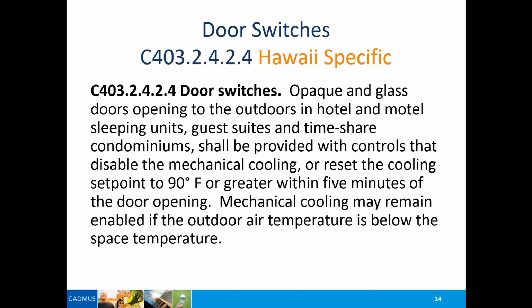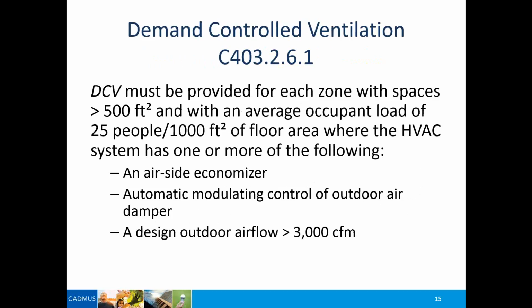All right. Demand controlled ventilation. If you have a building that requires a significant amount of outdoor air for ventilation loads, what we're doing right now is bringing in a lot of outdoor air, cooling that outdoor air, and then exhausting it. Say a health club, for example, will bring in quite a bit of outdoor air to make sure there's a lot of ventilation air in that space. We need to be able to capture the energy loss.